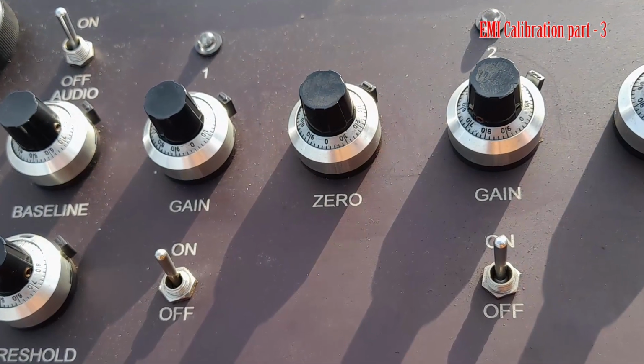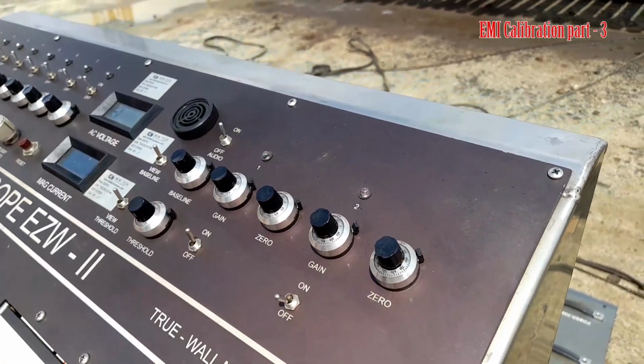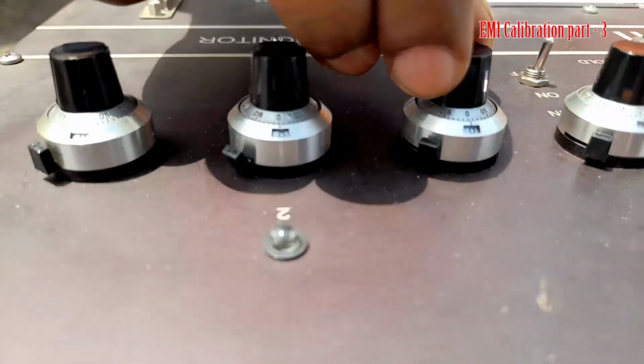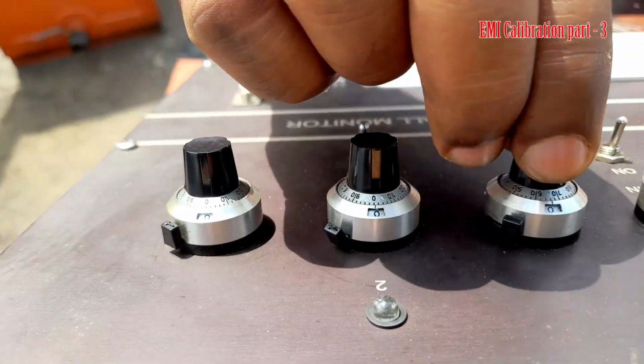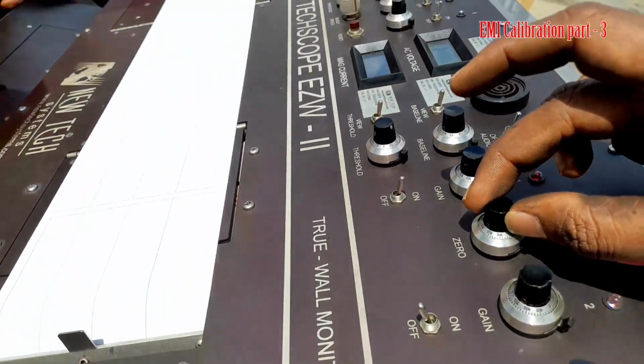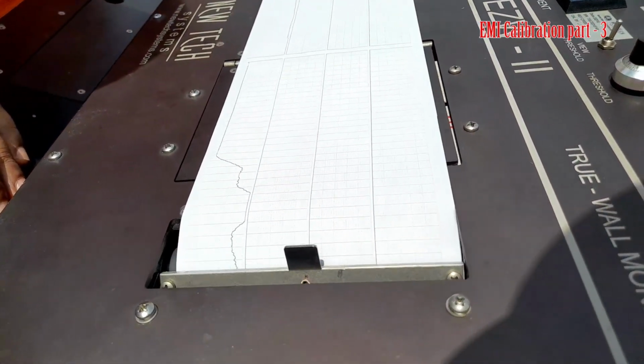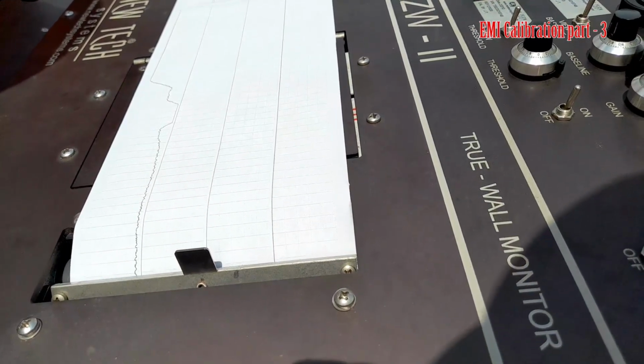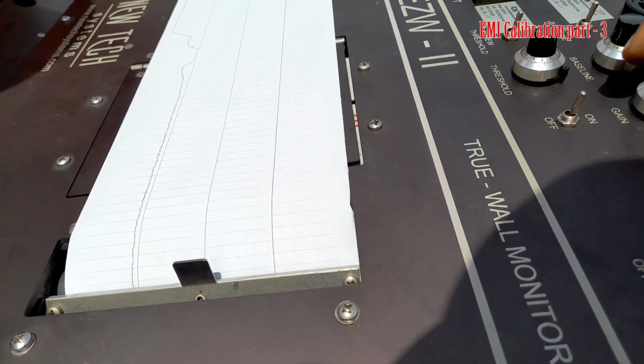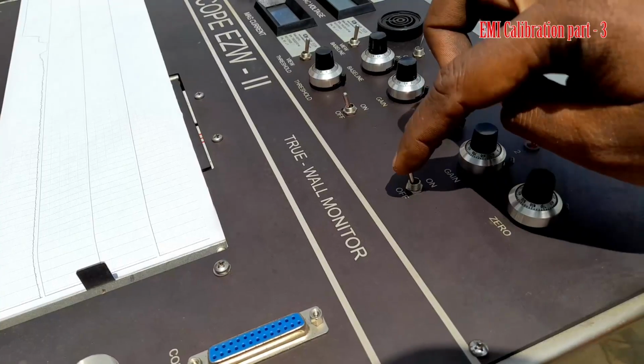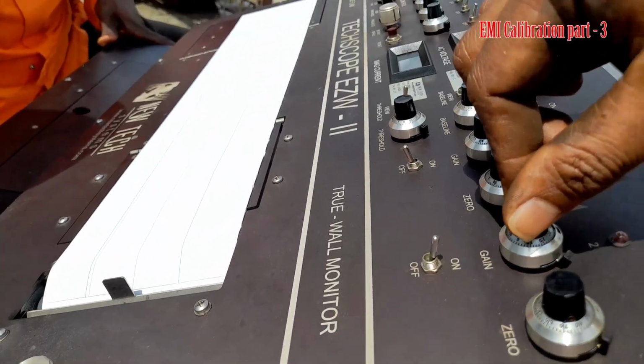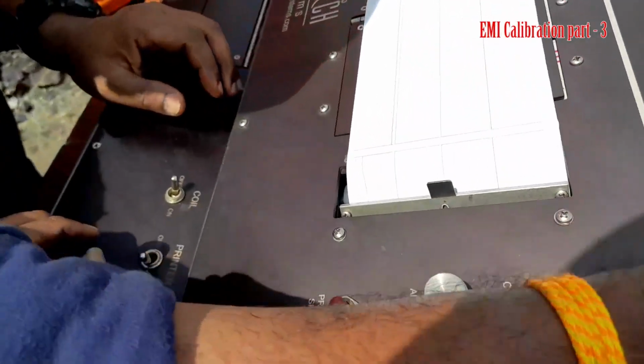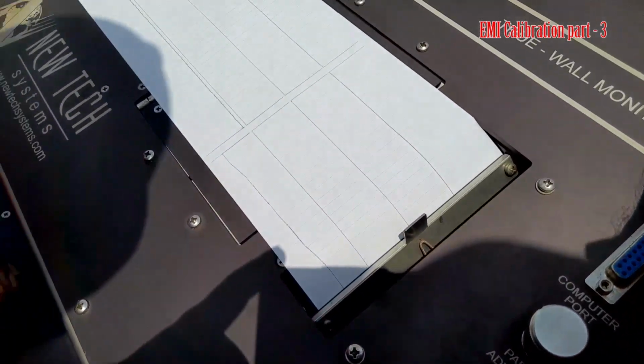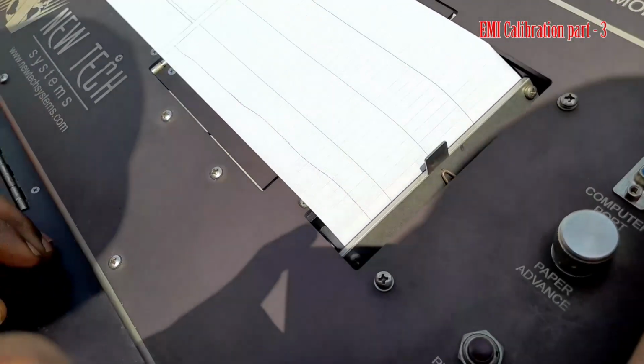First, switch on wall monitoring section 1. Then run the chart, adjust the 0 and gain to get the wall loss kick, the wall loss indication on the graph. If you get it in the middle of the graph, the kick is not passing the threshold, so you have to adjust the gain. Repeat the same technique for the second section. Switch on the second one, run the chart, adjust the value. After completing both setups, switch on both toggle switches and run it. You can get the value in the proper place. This is the first method.